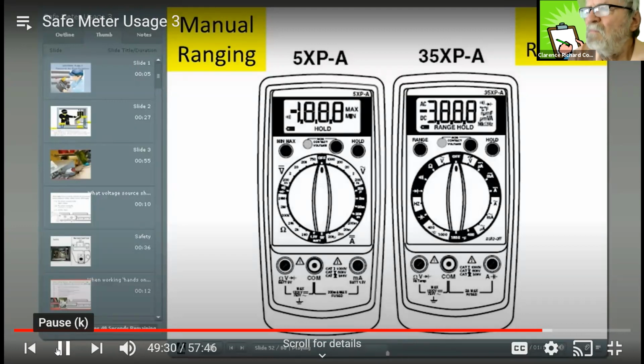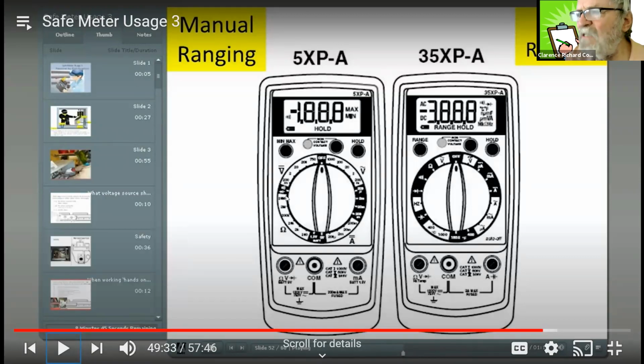The auto ranging meter requires special attention paid to the units of measurement. I'm saying up here, just because you have a number here and you have it on voltage, and if it says 120, doesn't mean 120 volts. It might be 120 millivolts. So you're going to have to look up here when this does its thing, to see what you're exactly doing there. If you put it on both, that's what you're kind of expecting, and then you see those numbers and you end up figuring that out a little bit better.